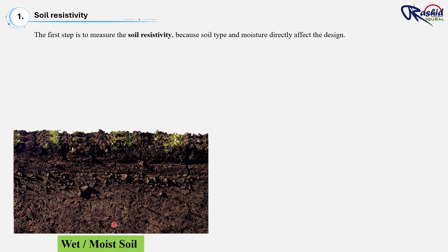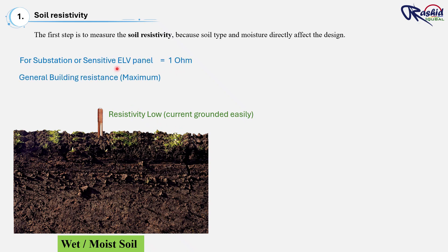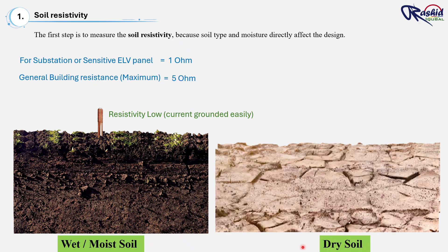The first step is to measure the soil resistivity, because soil type and moisture directly affect the design. If soil is wet or containing good moisture, its resistivity is low, which means the current can flow easily through the ground. As a result, it becomes much easier to achieve the target earth resistance. Typically below 1 ohm for substations or sensitive ELV panels, and below 5 ohms for general building earthing. If the soil is dry or sandy, it doesn't conduct electricity well, so current cannot flow easily. In such cases, resistance stays high until the electrode reaches moist soil or the water level where it drops and earthing becomes effective.